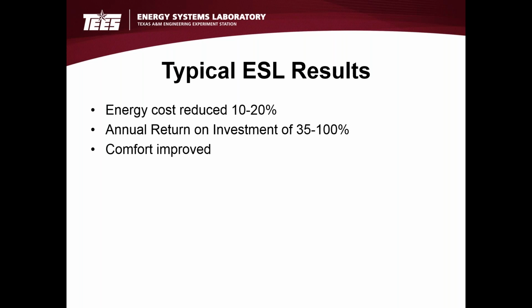Just to give an idea of the kind of results that can be achieved by this process, our experience in dozens, if not hundreds, of buildings that we have worked in is that we will typically reduce the energy cost by 10 to 20%. And the process typically is not installing any new equipment. So we're talking, the investment is basically in the engineering time that goes into the process, along with any deferred maintenance that is discovered that is causing major inefficiencies, and this is often significant.